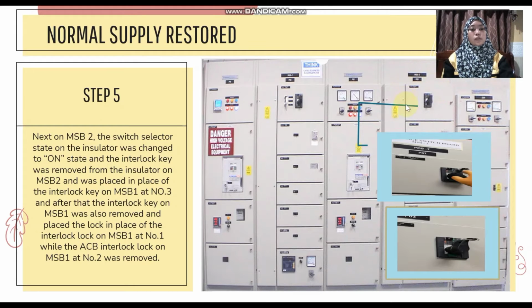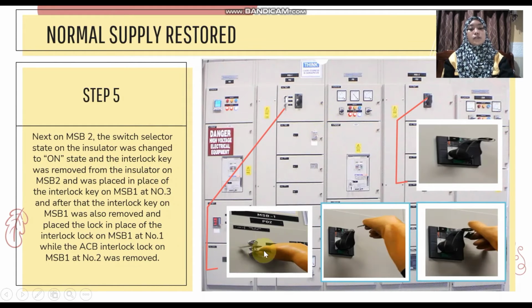Now on MSB number 2, for step number 5, at MSB number 2, we select the insulator to the on state. After that, we remove the interlock key here and bring it to MSB1. At MSB1 we have the place for the interlock key, which is here.